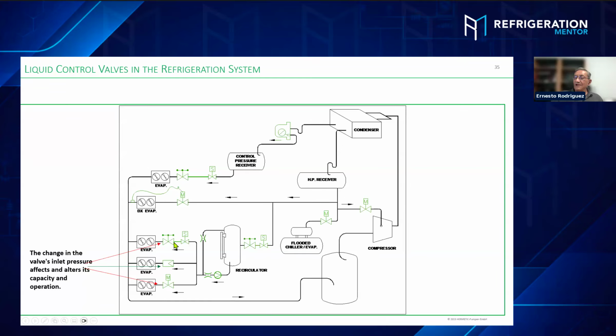The pressure at the inlet of the hand expansion valve is going to minimize, meaning this valve is going to be the loss calibration, because you calibrate this valve to have, for example, a 45 psi differential to maintain the liquid at the temperature in this evaporator. When you reduce the pressure right here, this loses calibration. The same way with the motorized valve. Yeah, that makes sense.